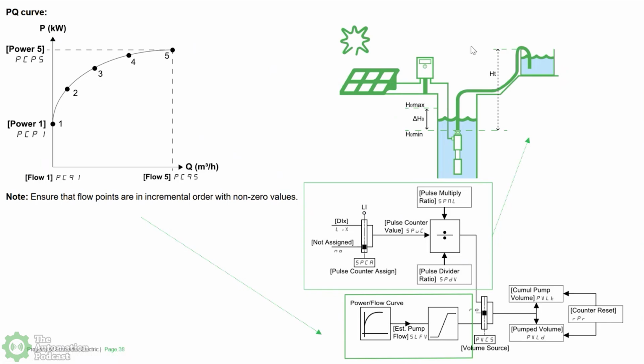So going back to our very cool diagrams, this is what it looks like. The flow estimation on the bottom is based off the VFD itself, and then the pulse counter: how to set that up, program, calibrate, and do our volume counter on the right, whether it's the daily counter or the reset counter with whatever we program onto there, monthly, yearly, and be able to record the flow.